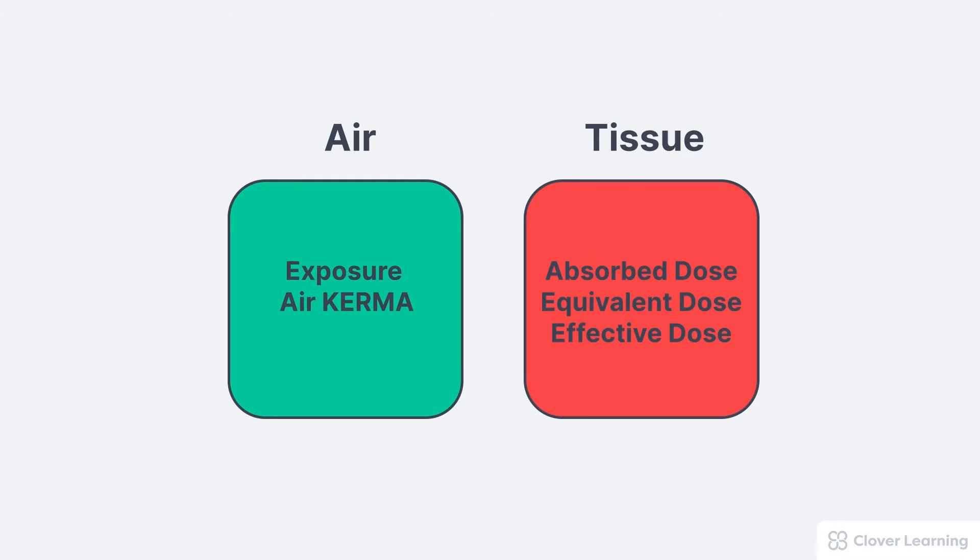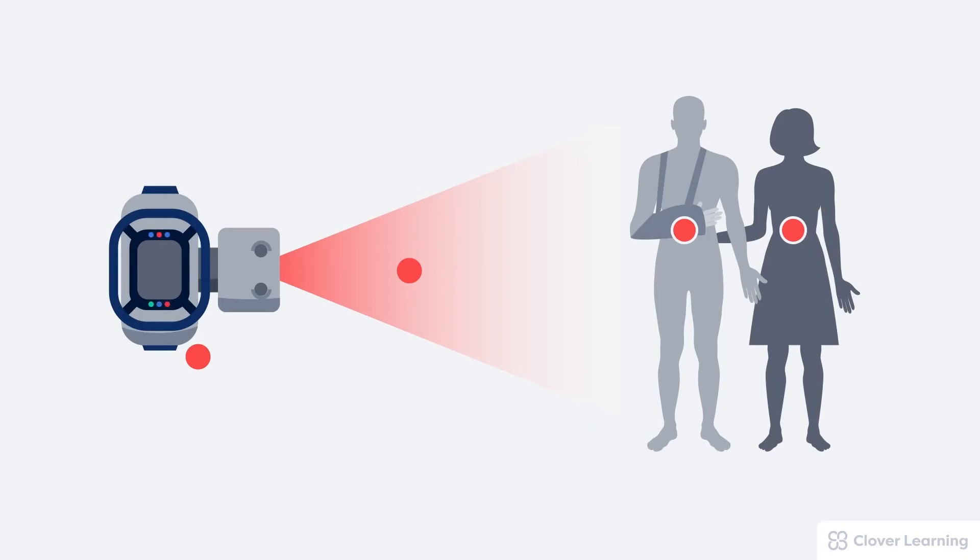All of these measurements are different, but related. Here's an example. If we wanted to, we could measure each of these values during a single x-ray exposure. The intensity of the x-ray beam is usually measured as the exposure or the air kerma. These values tell us how much radiation is coming out of the x-ray tube and is directed at the patient. We could also use the air kerma and exposure to measure the leakage radiation escaping the tube housing.